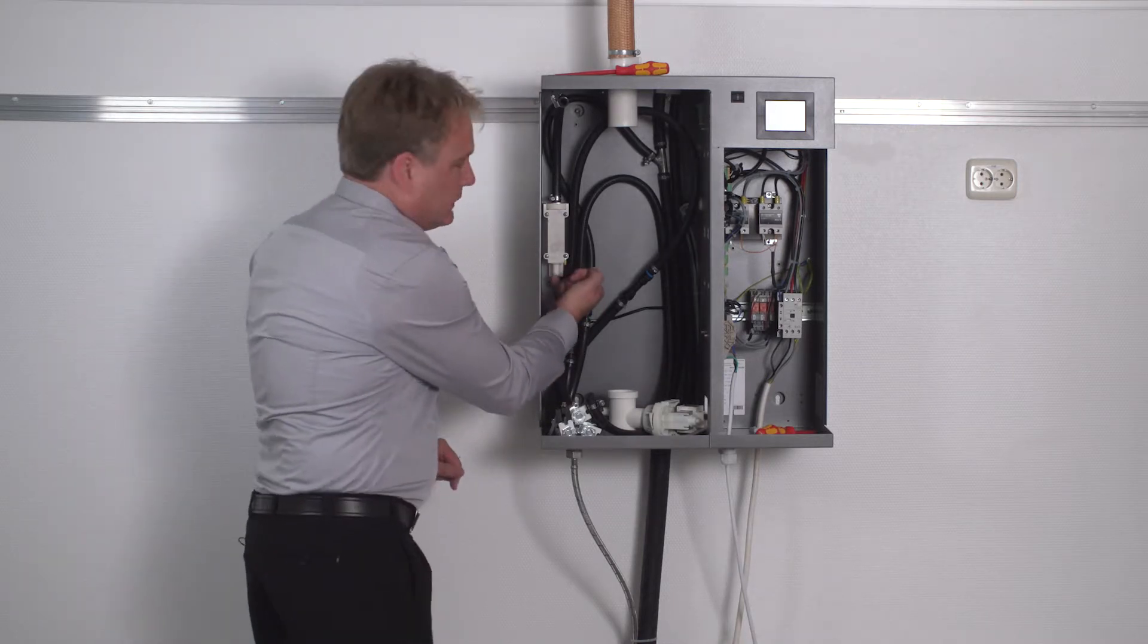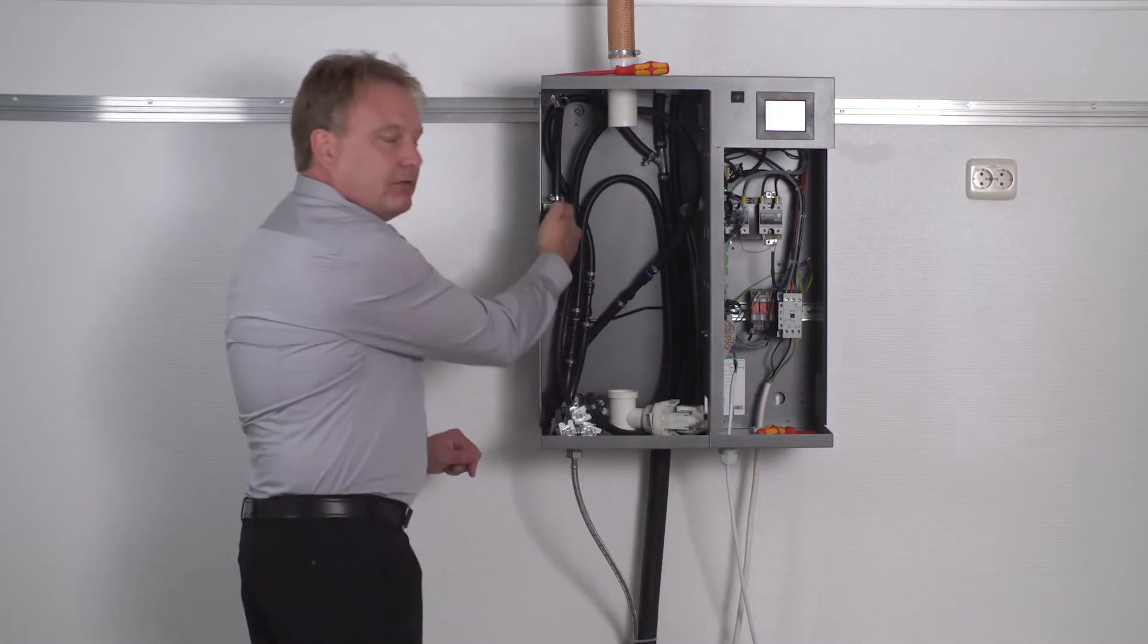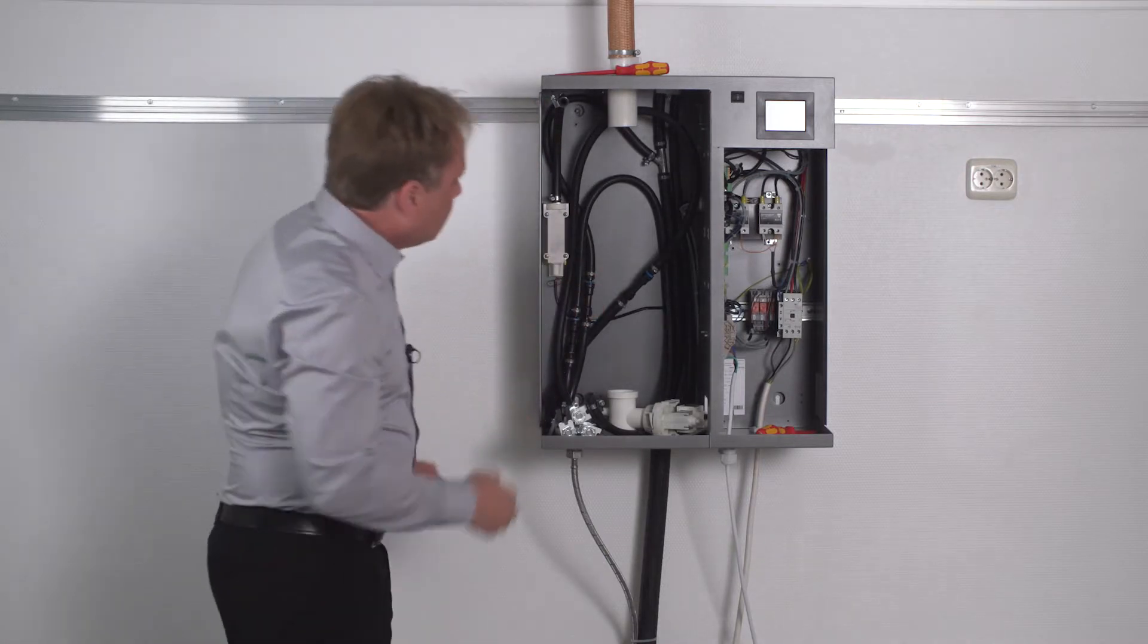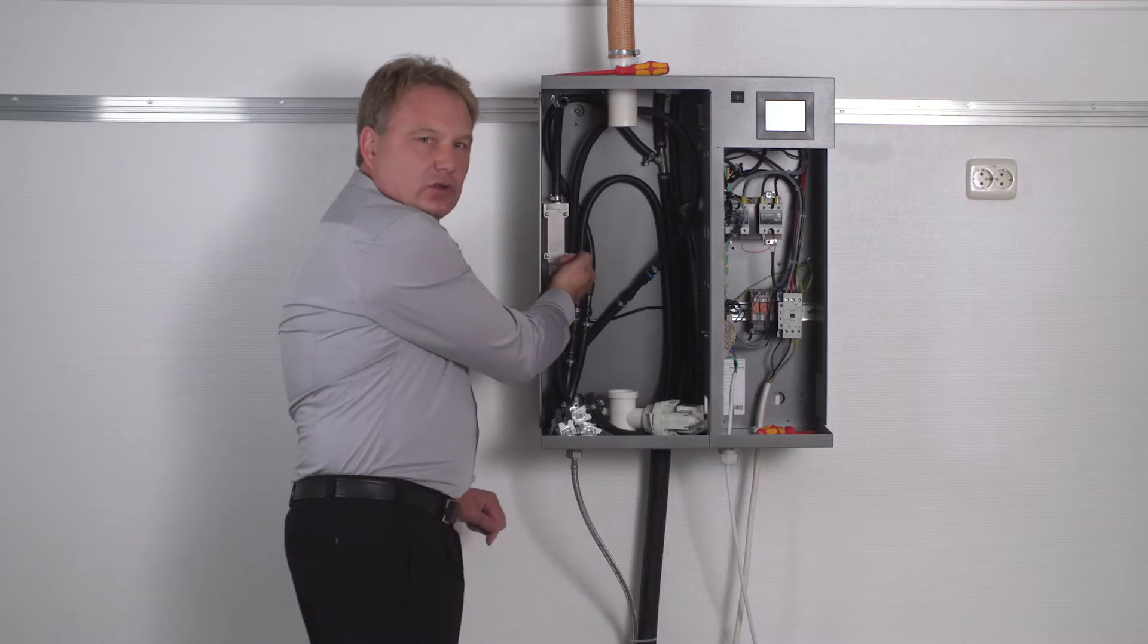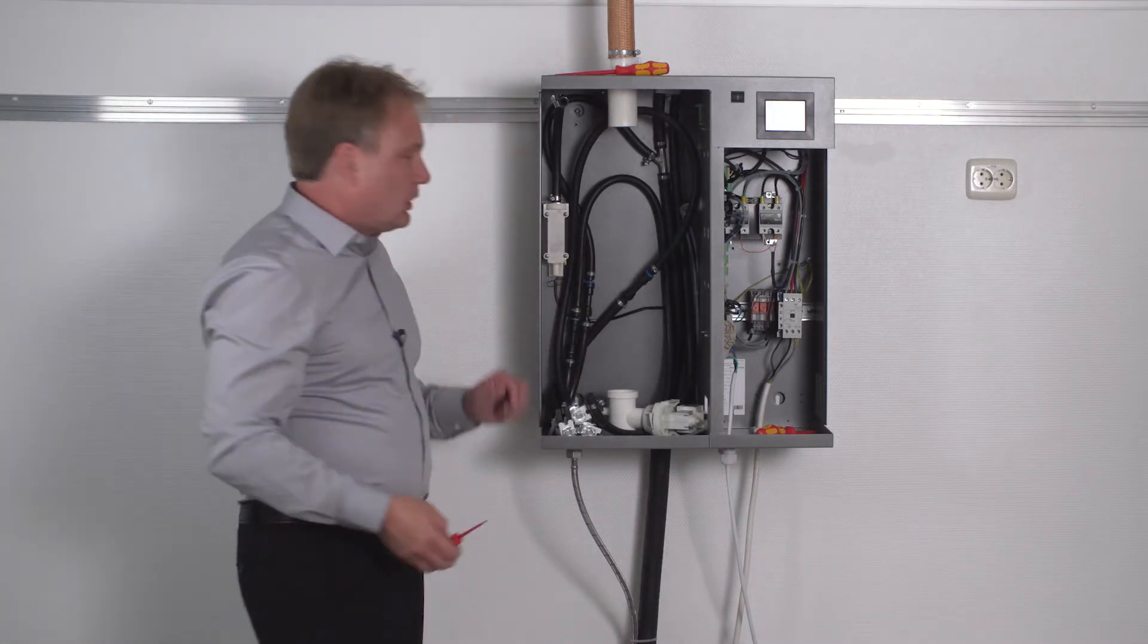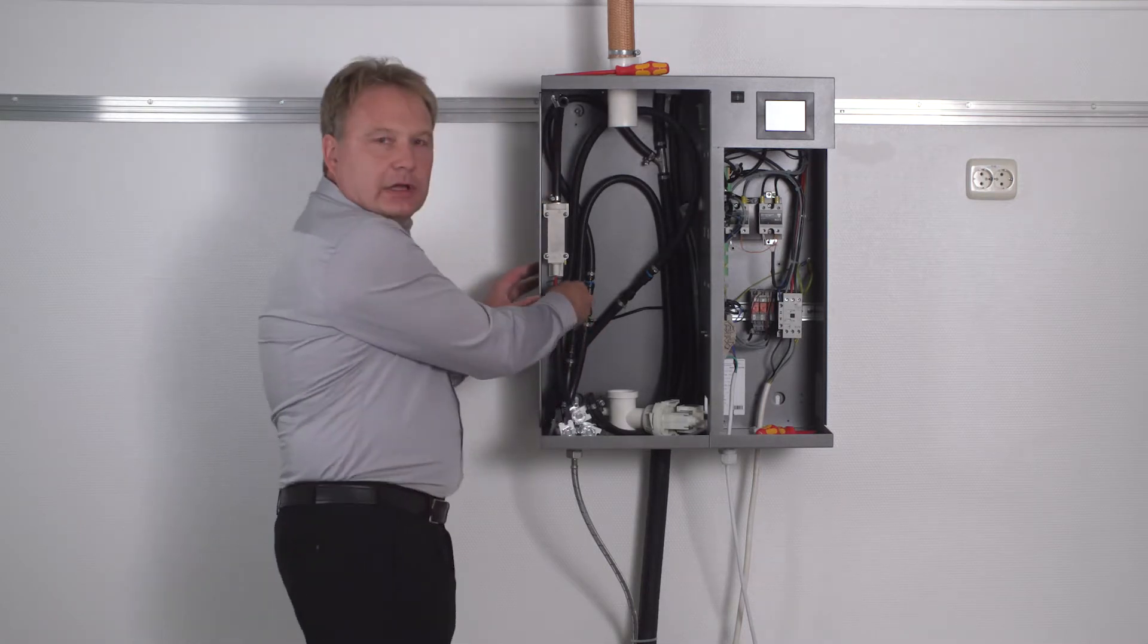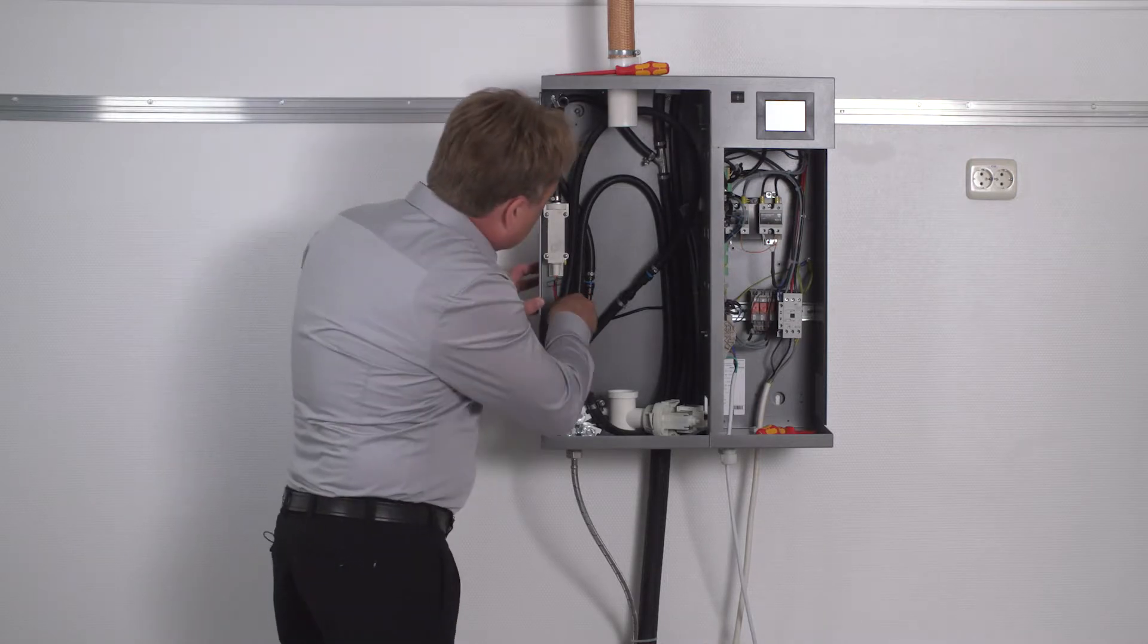Next, I will take a look at the water level control device, which is here. This water level control device must have a clear inlet. If it is clogged, in very rare cases, then take a screwdriver and push into it to loosen fine mineral deposits within.